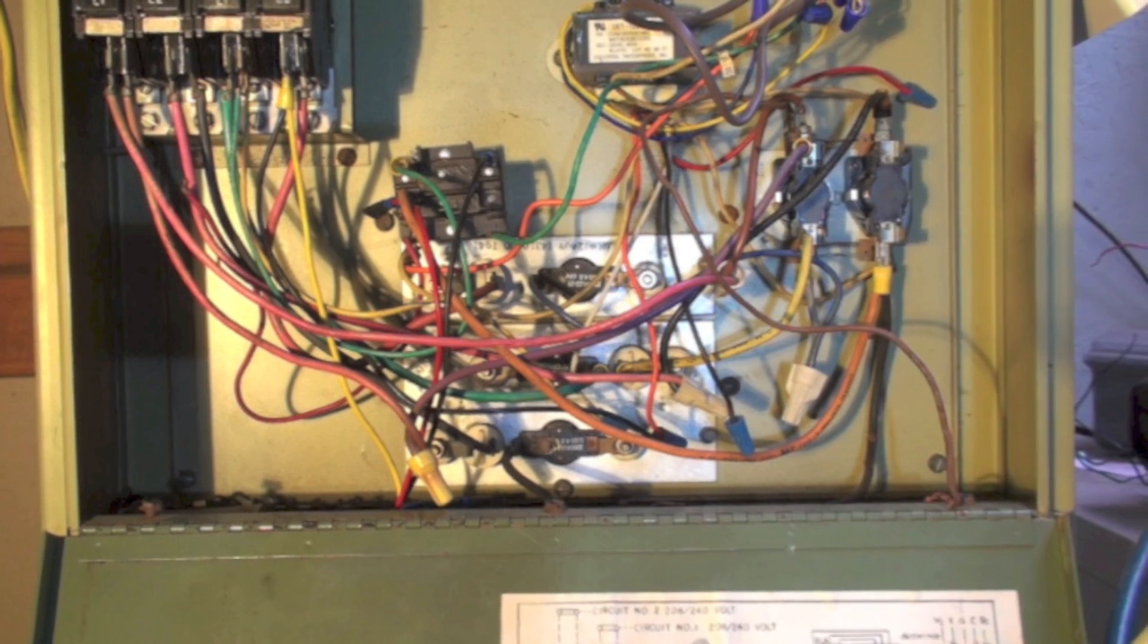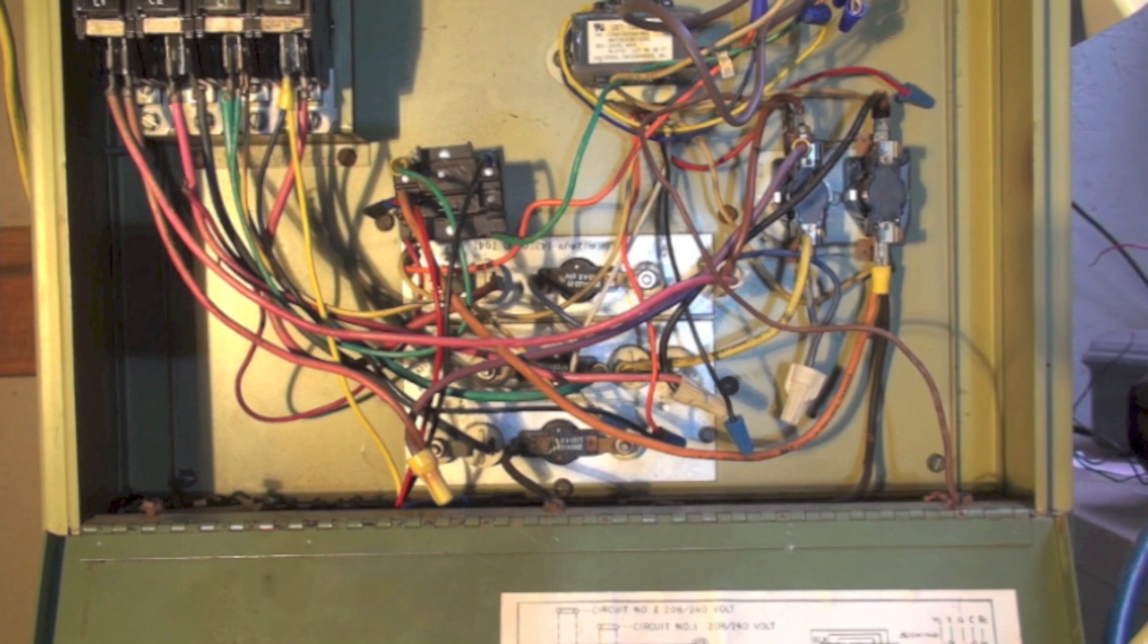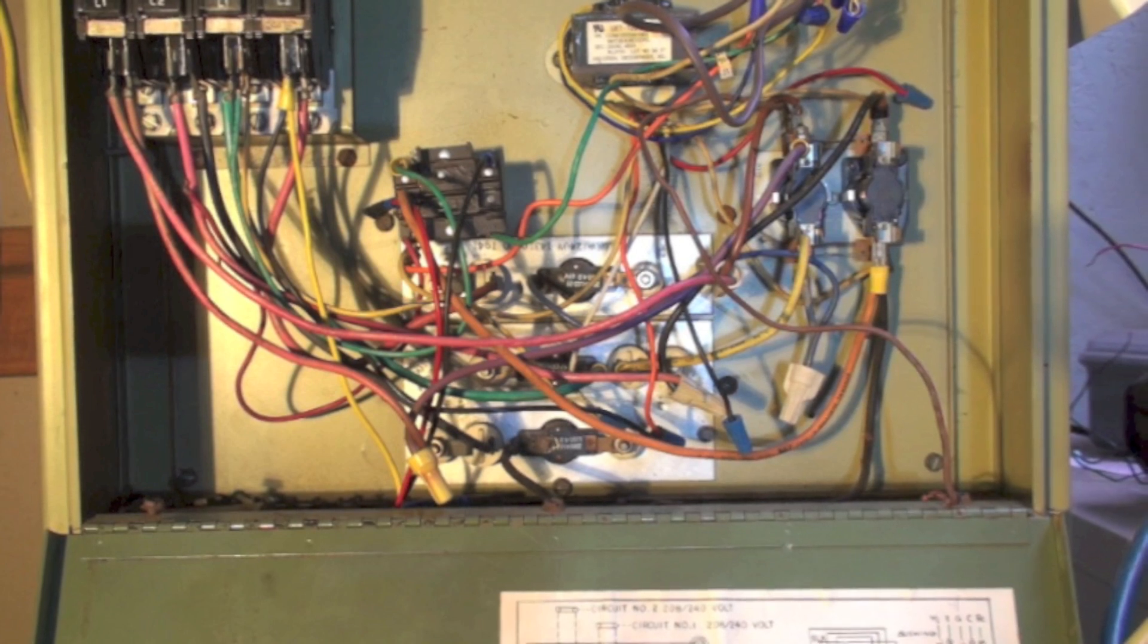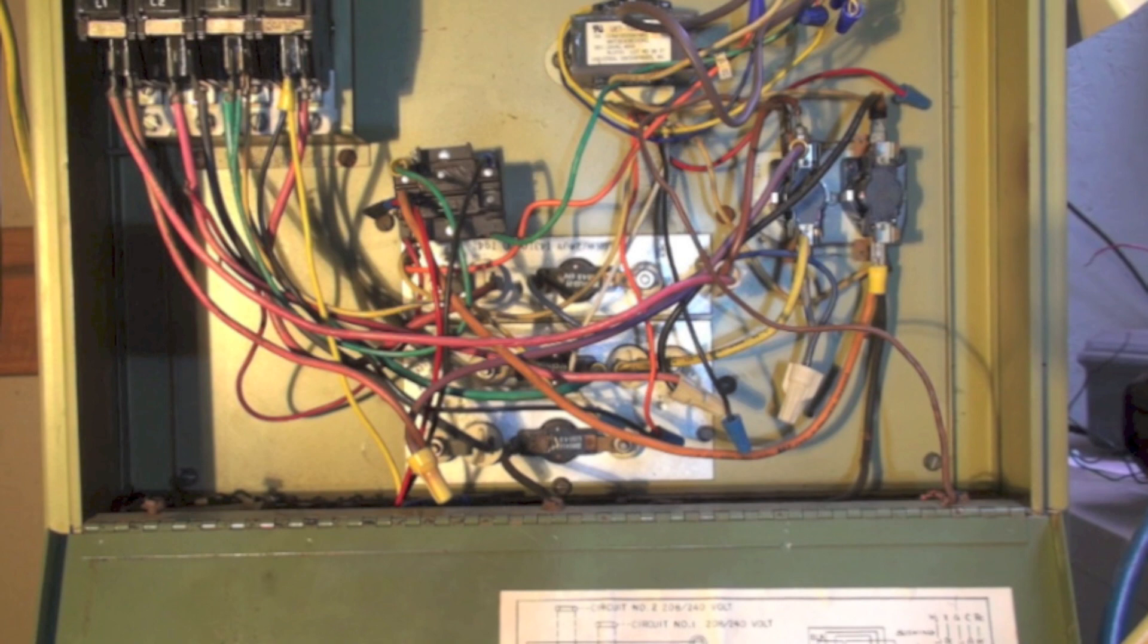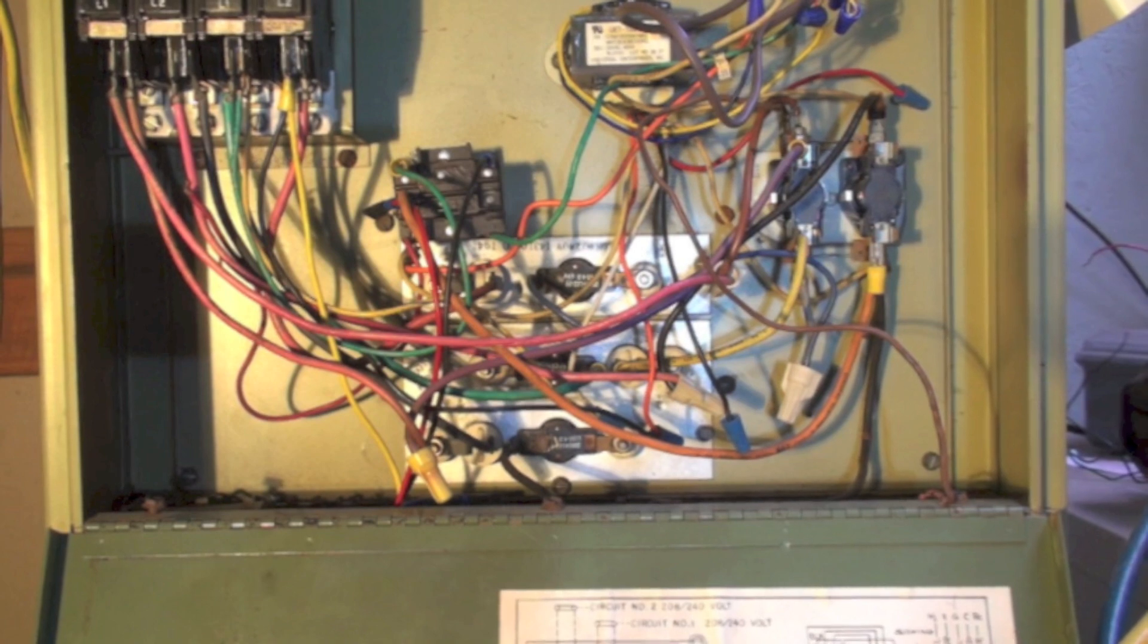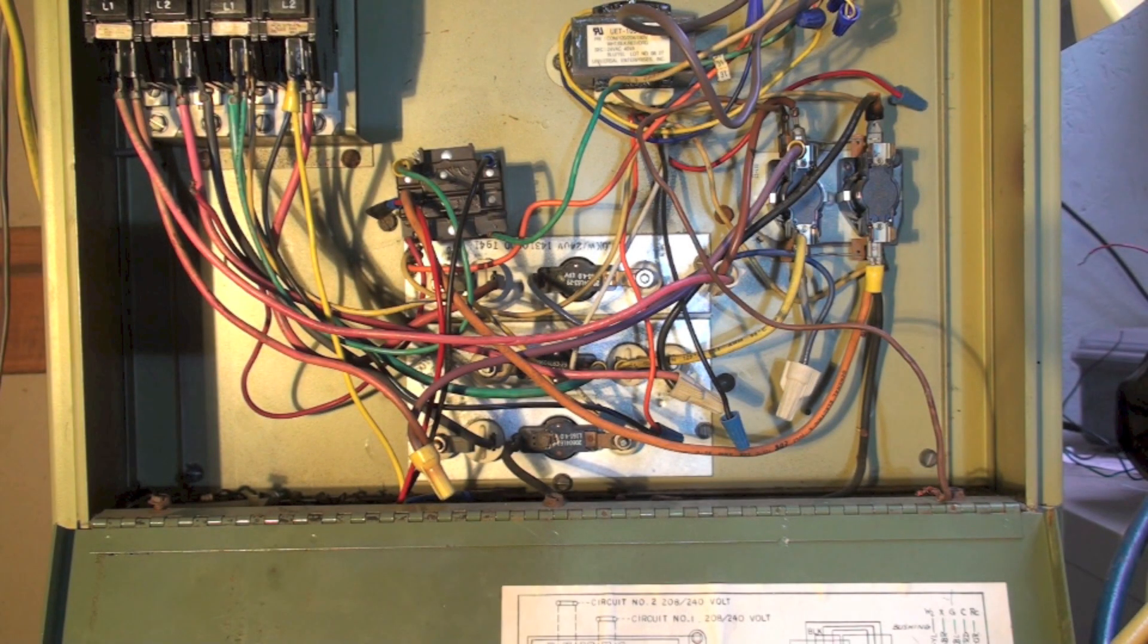Back to the job. To me, this is a better way to control these things than a sequencer. These sequencers are known for failure. I have put many contactors in these electric furnaces and I have yet to have one fail. I'll be going over a couple of things with this thing. First we're going to do a few repairs and then we're going to replace that sequencer.